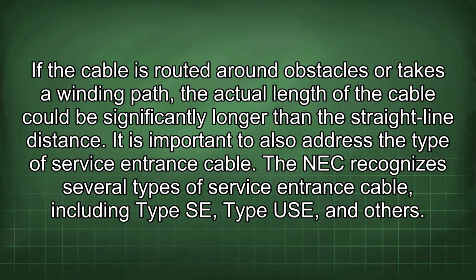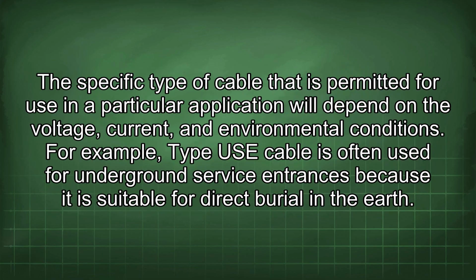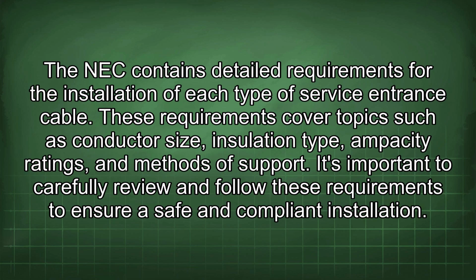It is important to also address the type of service entrance cable. The NEC recognizes several types of service entrance cable, including Type SE, Type USE, and others. The specific type of cable that is permitted for use in a particular application will depend on the voltage, current, and environmental conditions. For example, Type USE cable is often used for underground service entrances because it is suitable for direct burial in the earth. The NEC contains detailed requirements for the installation of each type of service entrance cable. These requirements cover topics such as conductor size, insulation type, ampacity ratings, and methods of support. It's important to carefully review and follow these requirements to ensure a safe and compliant installation.